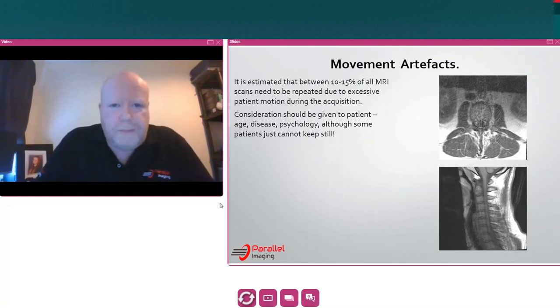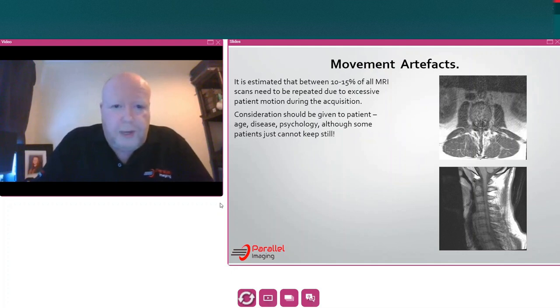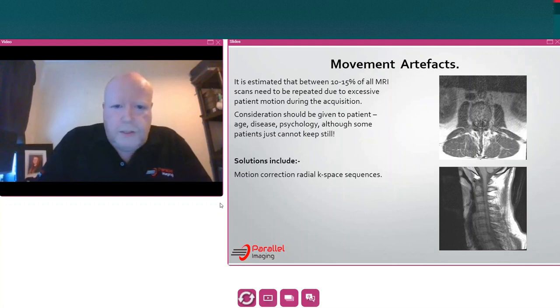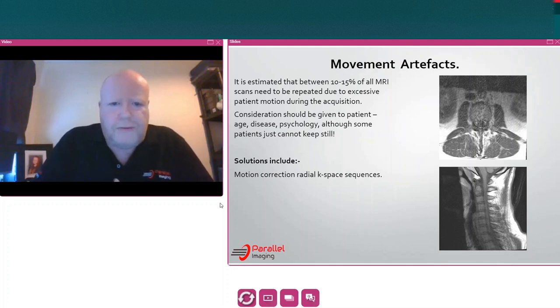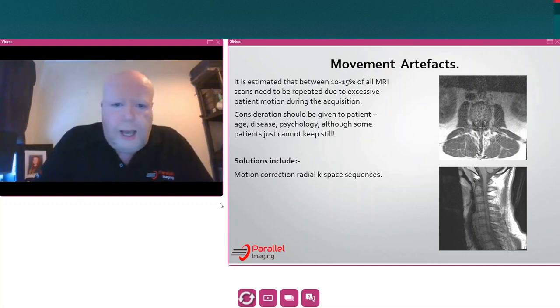We need to give consideration to the actual patient as to why they're moving. Age can be a factor, the disease process, the patient's psychology — although some patients just cannot keep still, as we see day-to-day. Some solutions: motion correction sequences are now available, and these tend to use a radial k-space filling technique. Examples are Propeller for GE and Blade on Siemens.